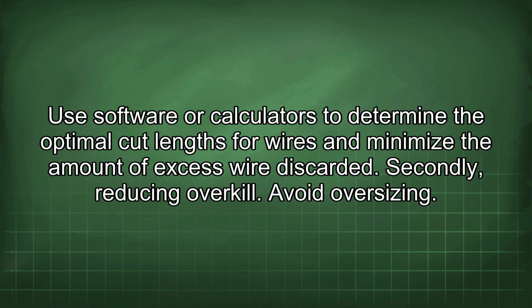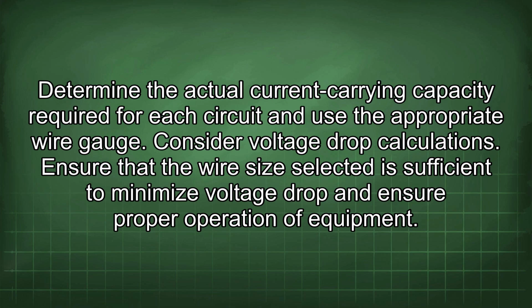Secondly, reducing overkill. Avoid oversizing by determining the actual current carrying capacity required for each circuit and using the appropriate wire gauge.